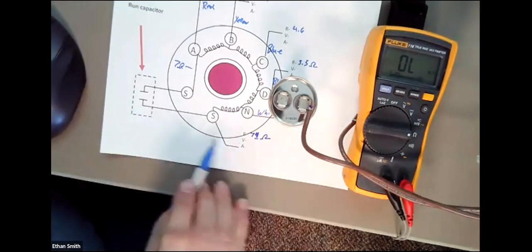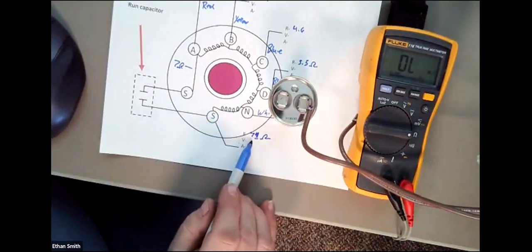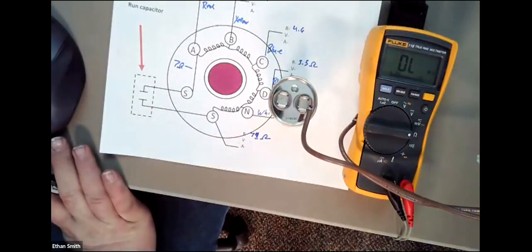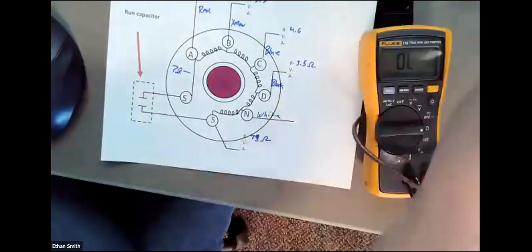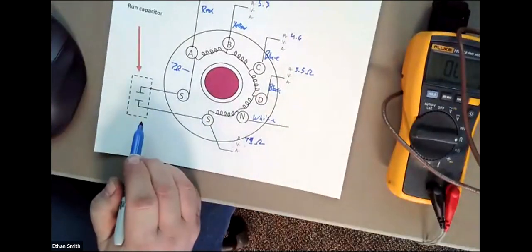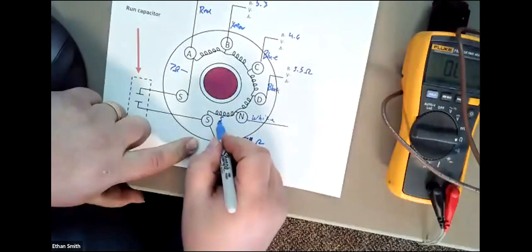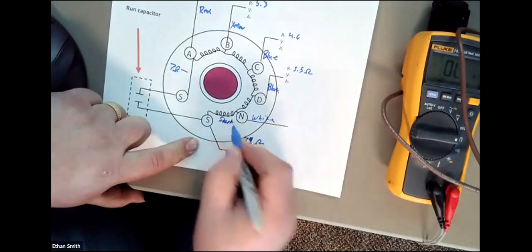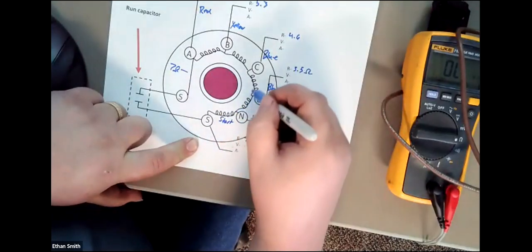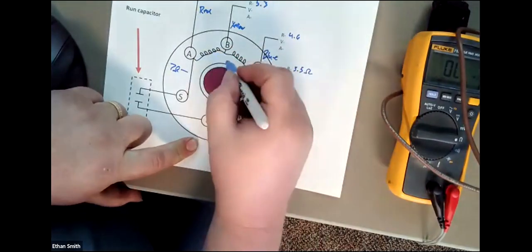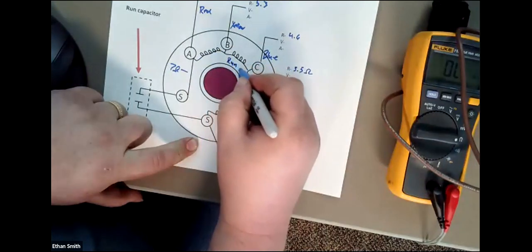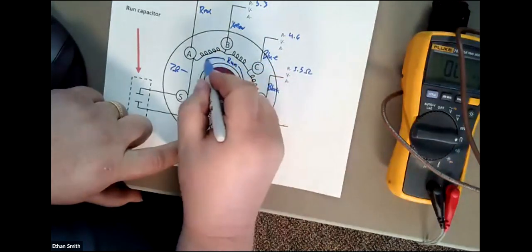Why do you guys suppose that this little piece of winding here is such a high resistance? Is it the start winding? That is the start winding. So this is the start winding. And then all of this would be considered our run winding, all the way down to neutral.